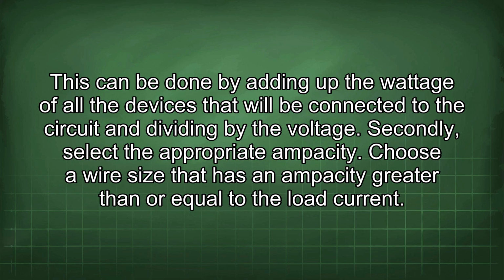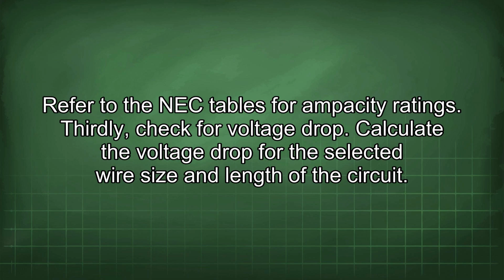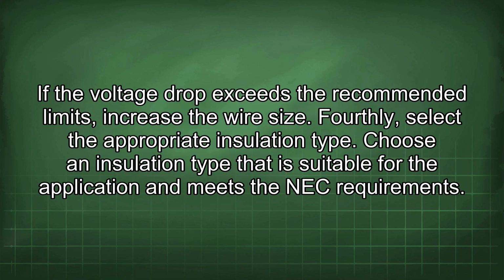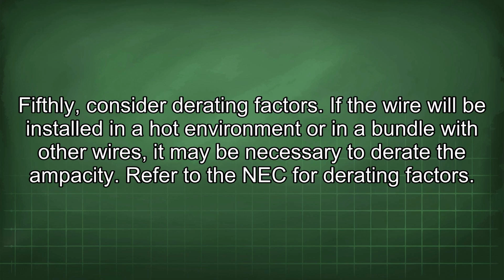Secondly, select the appropriate ampacity. Choose a wire size that has an ampacity greater than or equal to the load current. Refer to the NEC tables for ampacity ratings. Thirdly, check for voltage drop. Calculate the voltage drop for the selected wire size and length of the circuit. If the voltage drop exceeds the recommended limits, increase the wire size. Fourthly, select the appropriate insulation type. Choose an insulation type that is suitable for the application and meets the NEC requirements. Fifthly, consider derating factors. If the wire will be installed in a hot environment or in a bundle with other wires, it may be necessary to derate the ampacity. Refer to the NEC for derating factors.